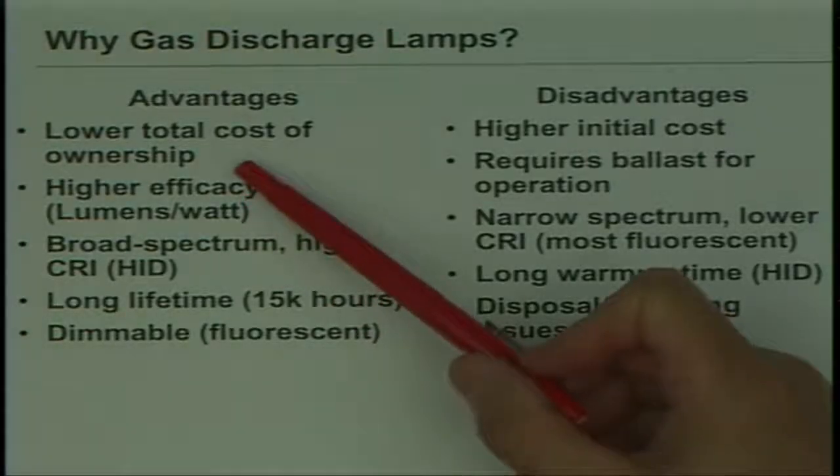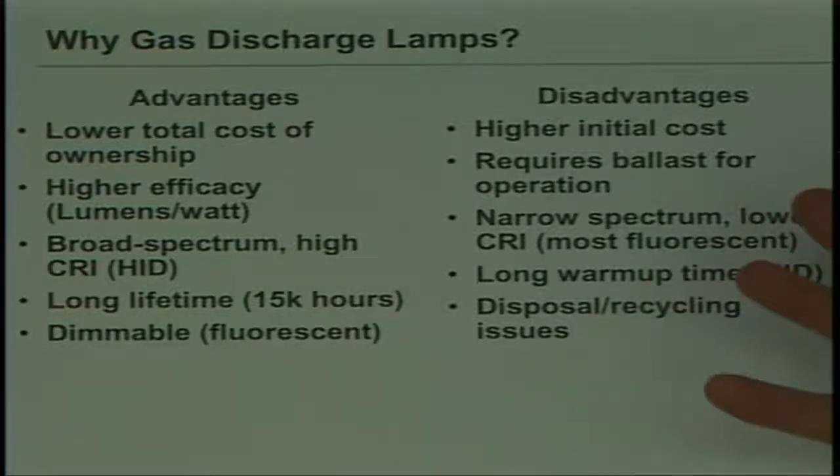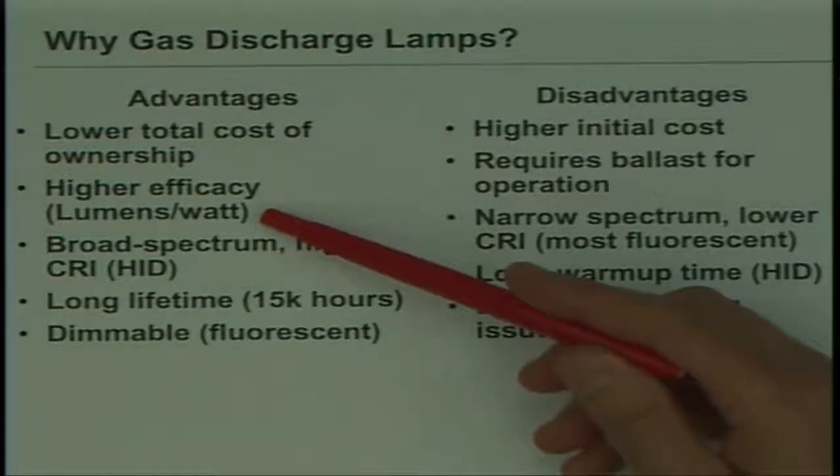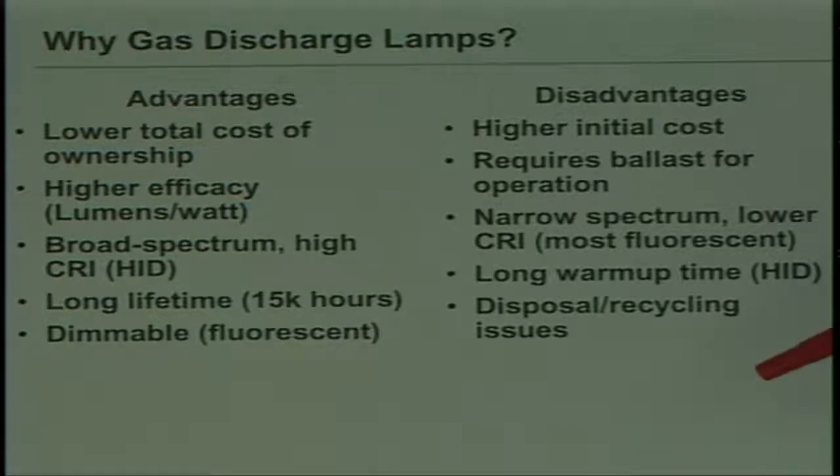Looking at advantages and disadvantages, you can get a lower total cost of ownership. You invest more upfront in the lamp, but theoretically you get a longer lifetime. Those of you who have bought CFLs at Home Depot and been promised 20,000 hours are probably wondering, do you really get a lower total cost? So there's a higher initial cost. If they're well designed and used properly, they should give lower total cost of ownership. They provide higher efficacy and more lumens per watt. Typically, compared to a traditional incandescent lamp, you get about four to five times higher lumen efficacy from a fluorescent lamp.